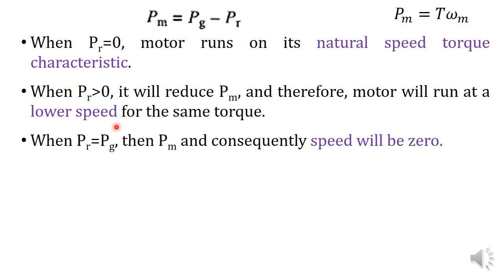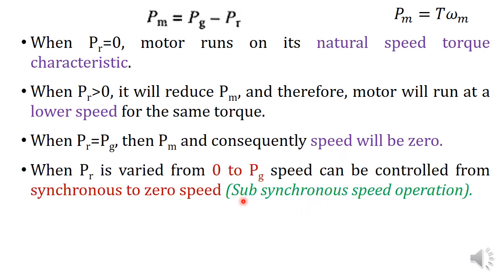Another case: when Pr = Pg, both powers are equal, meaning there is no mechanical power developed — Pm = 0 — and therefore speed will be 0. So by controlling Pr from 0 to Pg, we can control the speed of the motor from natural speed ωms down to 0. This is known as sub-synchronous speed operation — operation of the motor below synchronous speed, from zero speed to synchronous speed.